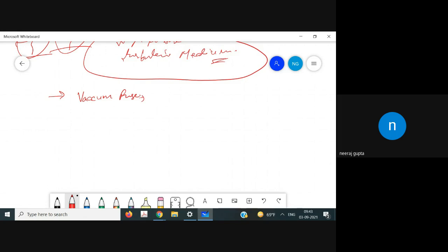So in that very case, you can say that the design, operation, and current-voltage relationship of this fuse is similar to that of the expulsion type fuse. The main difference in the case of vacuum is that it is a completely sealed unit, and no expulsion action is there in that.